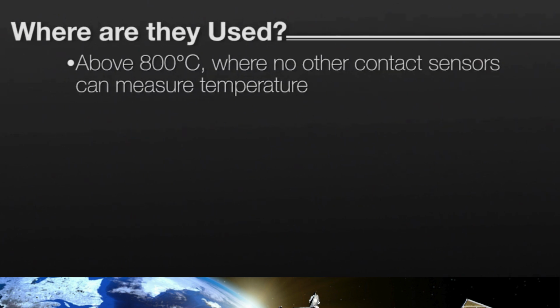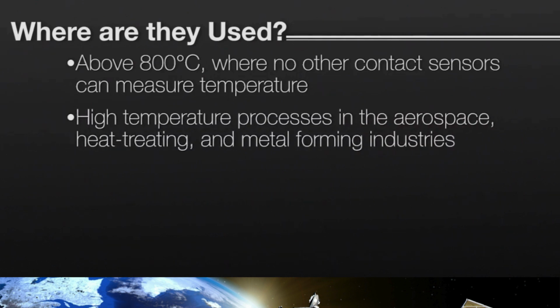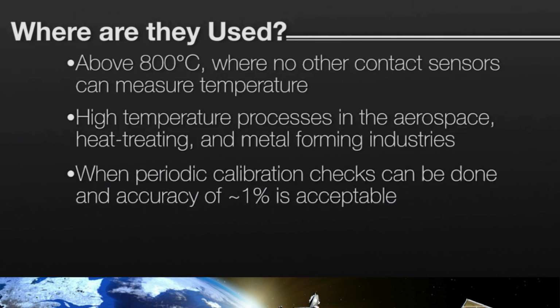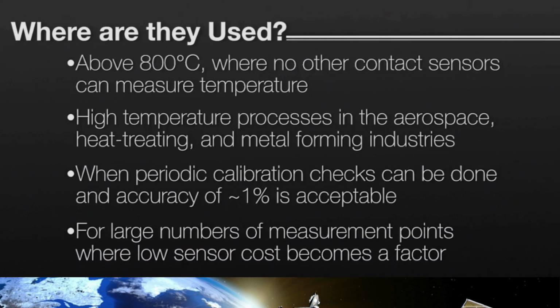Thermocouples get used mostly for low-cost contact temperature measurements above 800 degrees C. And as such, you find heavy usage in the aerospace, the heat treating, and the metal forming industries where people have no choice but to use thermocouples. Sometimes people use them for their lower cost than RTDs, as long as they don't mind recalibrating or replacing the thermocouples annually. Some applications like automotive or aerospace engine test stands require hundreds of measurement points, and then cost competitiveness of the temperature sensor becomes a bigger factor in a user's decision-making of which temperature sensor to use.